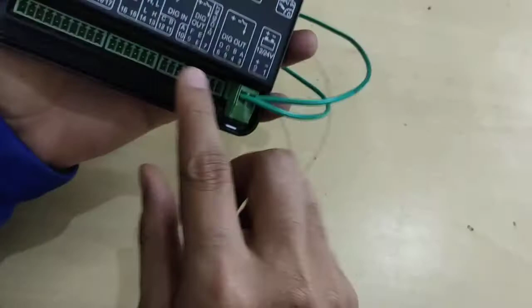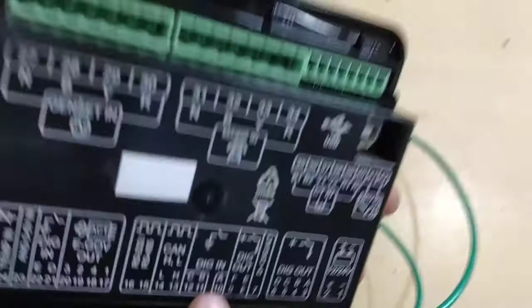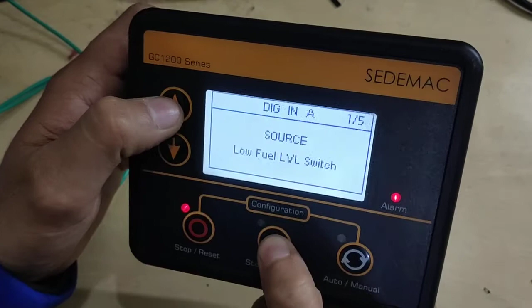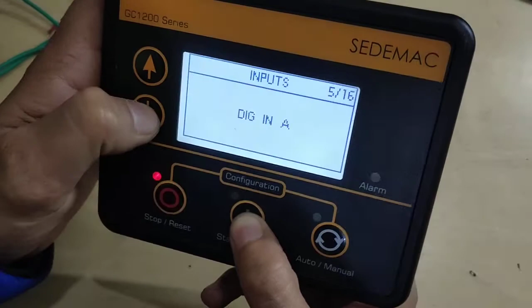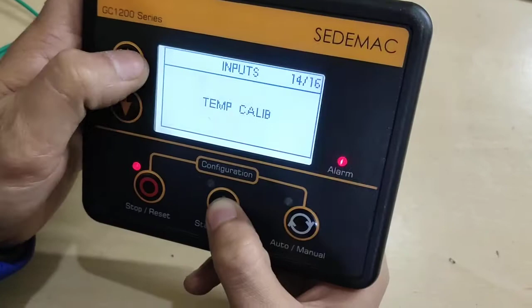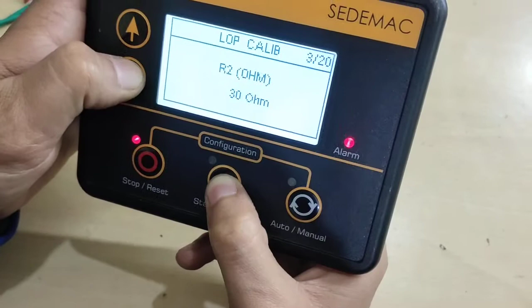Digital input A, B, C, like these inputs. So which input do you want to configure on these ports? You can adjust it here. This is a low fuel level switch, and on B, emergency stop is there. So here you can calibrate these LOP and temperature settings.